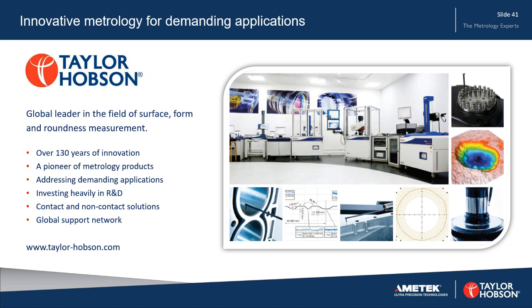And the next question here is, can we measure harmonics on an old Talyrond 73 instrument? The answer is you could measure to a certain level, but it will be limited because we don't have an encoder built in that actually tracks exactly where the stylus is as it rotates. Not just that, but the older style of instruments, whether they're from Taylor Hobson or from other manufacturers, and the older methods were used by timing the measurement.